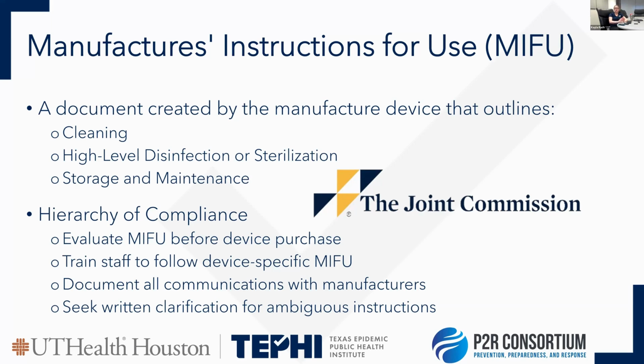And before you start monitoring, or if you are sitting in your purchasing committee and you're looking at new types of equipment, you always want to request the MIFU before purchasing. Make sure you get it and look at it, and see what type of instructions that IFU has, and if that is something similar to the equipment that you've used. Do you have the capacity to do what is needed, aka are you set up for the cleaning and storing of that piece of equipment? What type of training does staff need to handle that device, to clean it, store it, transport it, etc.? And also, is that something similar to the policies for your other devices within the organization? You also want to document any communication with the manufacturers. When you're sitting on the purchasing board and you're looking at a new piece of equipment, you can always reach out to the manufacturer and ask for the MIFU.